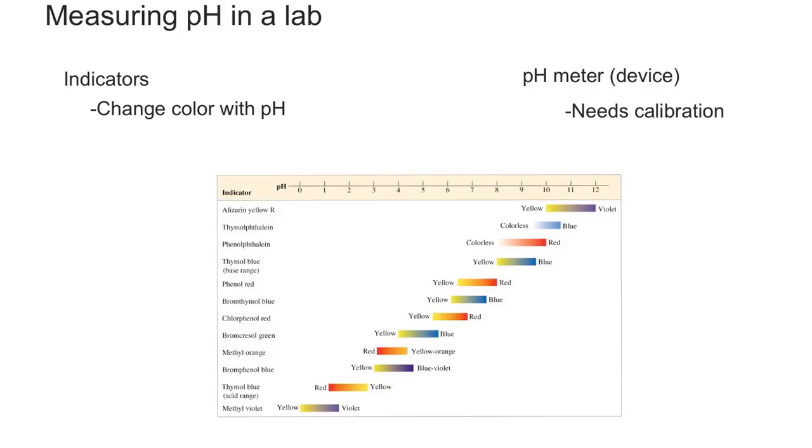The way it works is you have this device with a display that will show the number once you put in the part of the equipment that can measure the pH of the solution. Depending on your device, it might have a needle that you can submerge into your solution. And just like any electronic device, it needs to be calibrated.